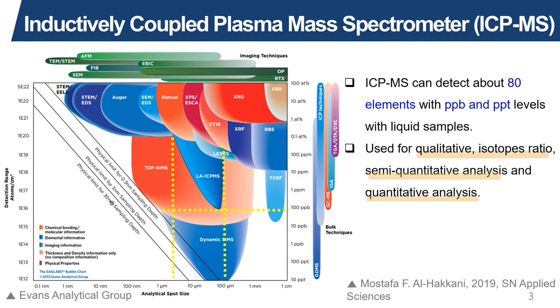As with every analysis technique, we first start off with the bubble chart of detection range against beam size. From the diagram, we see that the LA ICP-MS technique offers a chemical sensitivity down to roughly 100 parts per billion, and an analytical beam size of around 100 microns. Note that this technique is for the LA, or laser ablation ICP-MS technique, which is used primarily on solids.